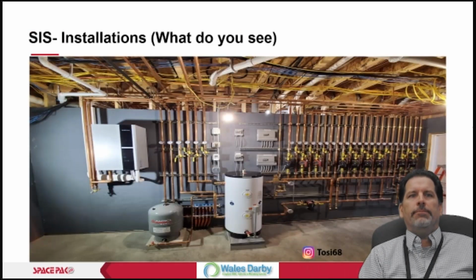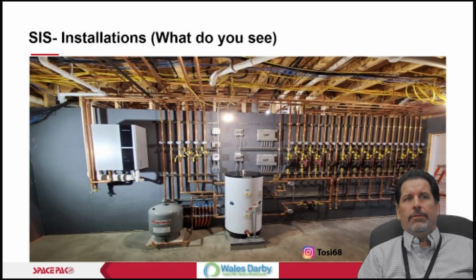I mean, this picture says it all. It says nothing about Wales Darby, but the picture itself, man, I would feel pretty comfortable walking in this room and I go, wow, what boiler is this? That's not a boiler at all. That's the indoor unit for our heat pump. And that's where we do our refrigerant to water exchange, right? Really, really hot gases or really, really cold for cooling or heating. And then we're just doing pumping and piping. Universal hydronics formula, GPM equals BTUH divided by (delta T times 500), and all things take over.